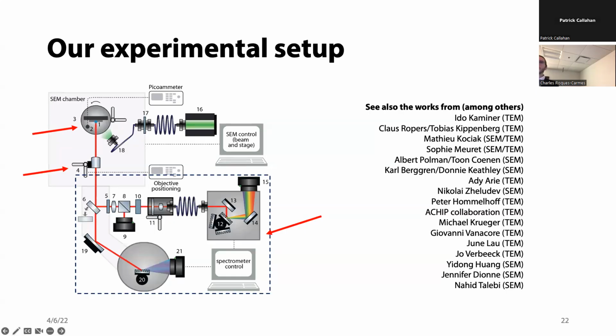In the visible, we also have a CCD camera that images the surface of the sample in order to do proper alignment. We have some excitation channels also to do alignment of the optical detection channel with the electronic excitation channel. And recently, we've started to move towards UV detection. So there we have everything under vacuum up to the UV spectrometer.